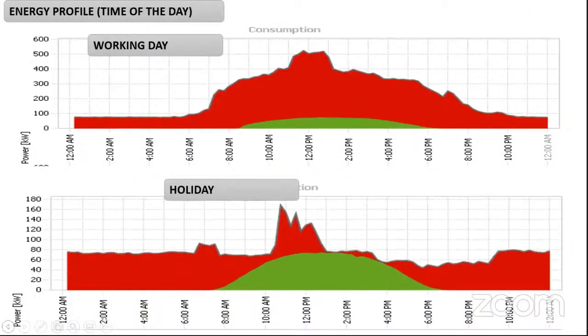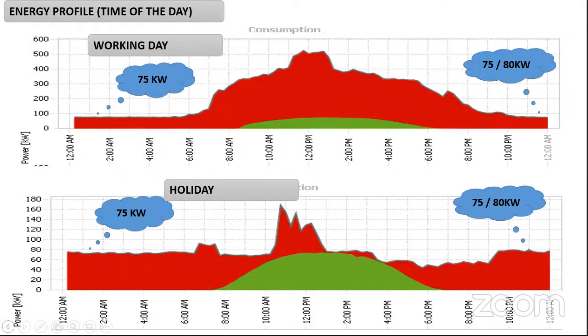Nobody cooks after 10 o'clock, but the blower is continuously on. And this is where we have a very good potential of reduction in power. So from that 60 units, we put the VFD, we put something on the blower, we put a programmable controller, and we could reduce this power of the blower by around 30-40% of the blower consumption. So this is something you should really look at.